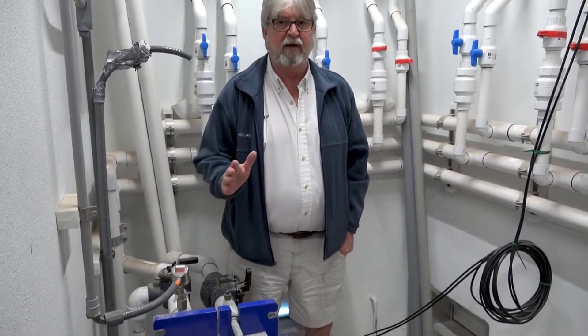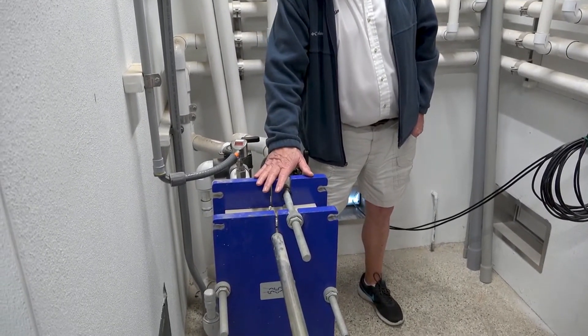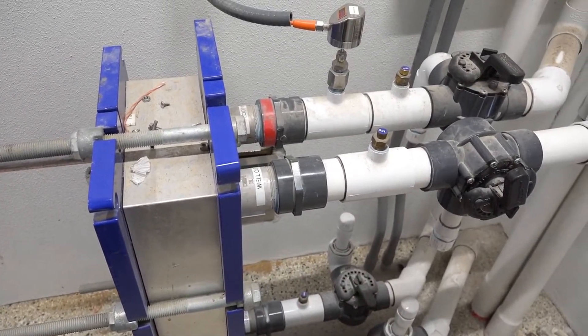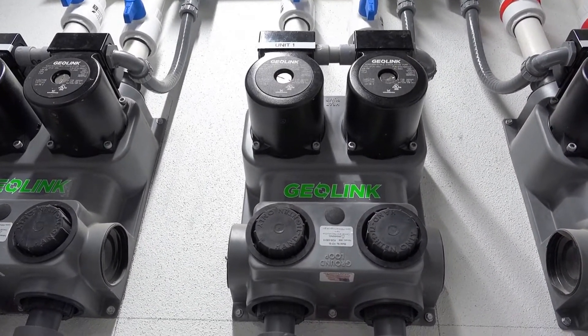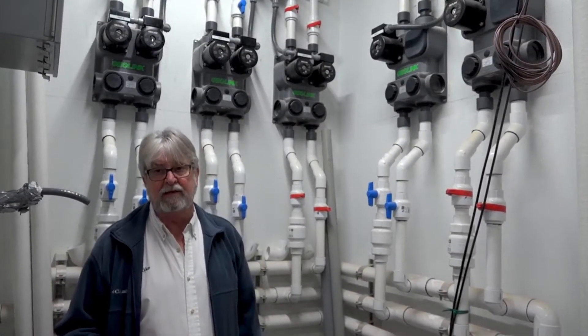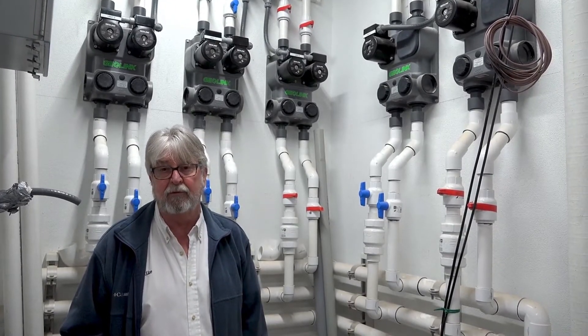Anytime we use well water as our source for geothermal air conditioning, we never let that water go directly through the system. So this is a titanium intermediate plate heat exchanger where it has well water on one side and closed loop water on the other side. To circulate the water through the closed loop, we have flow centers for each individual geothermal unit, so we can control that water to get the longevity out of these units that we would expect.